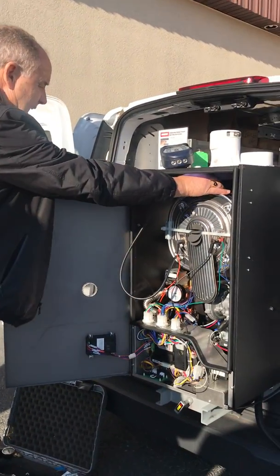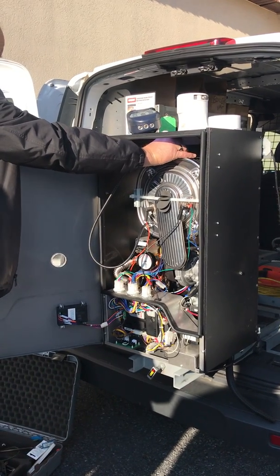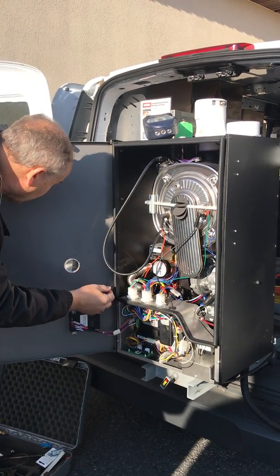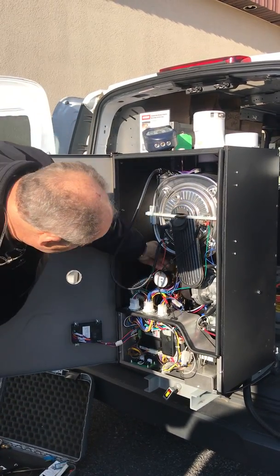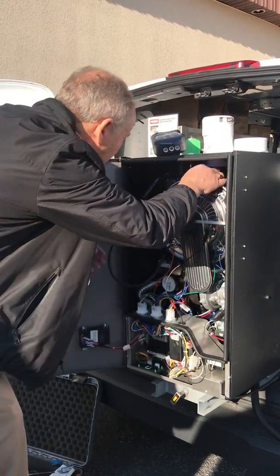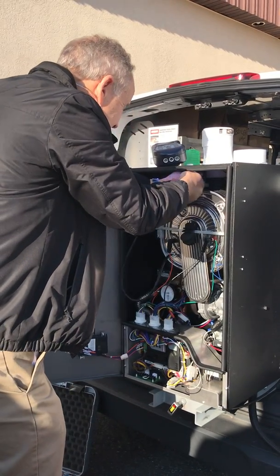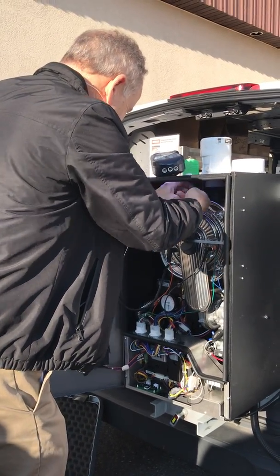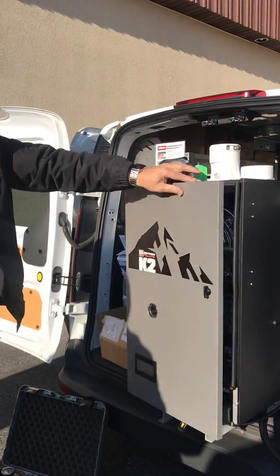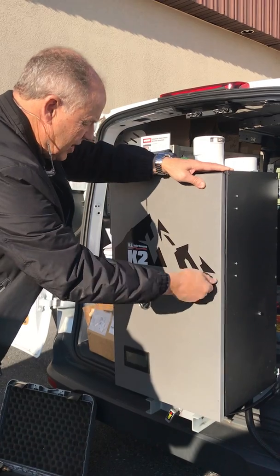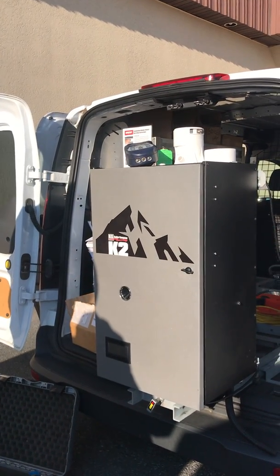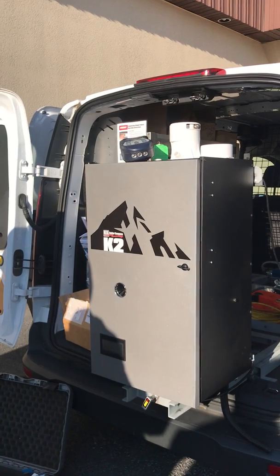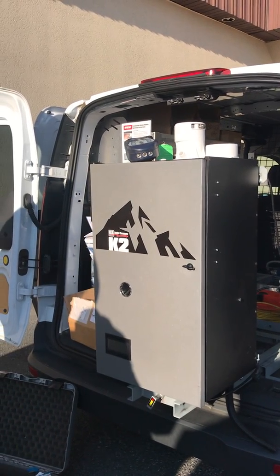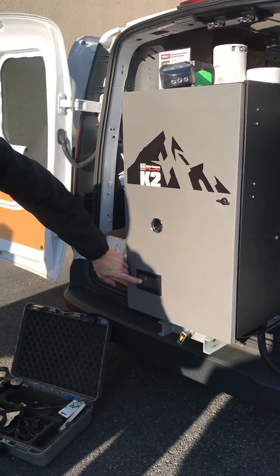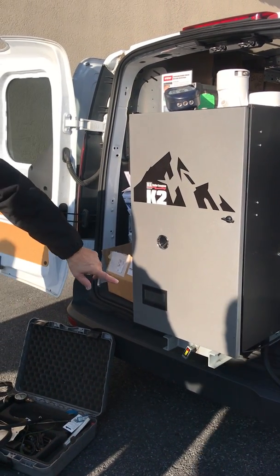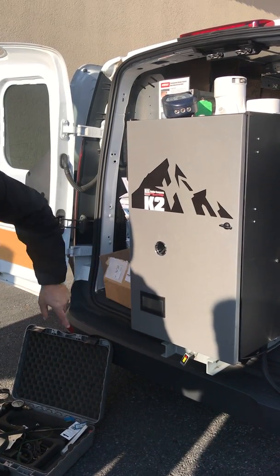These, they have a stack sensor on here. If you're ever working with this and you're not sure what's what, actually let me pull something off that I can actually get to a little bit easier. It's down here at the bottom. Okay, so it has a stack sensor in here, and if you ever came out to the job and it doesn't happen instantly, but you end up getting an error code that's on here, you actually get the help screen that flashes. And we'll do it upstairs, but if you get the help screen that flashes, you just go right through and it actually tells me fault status.